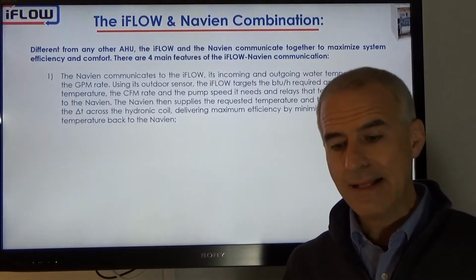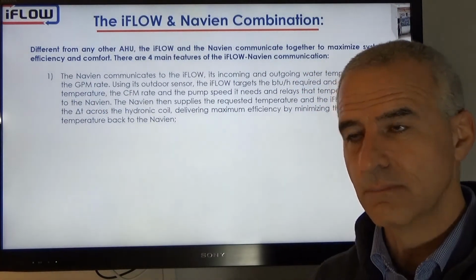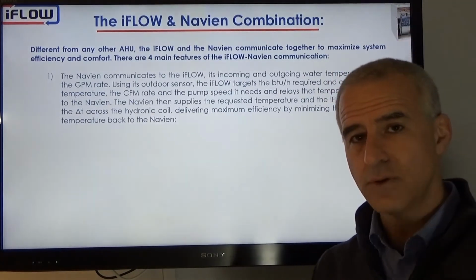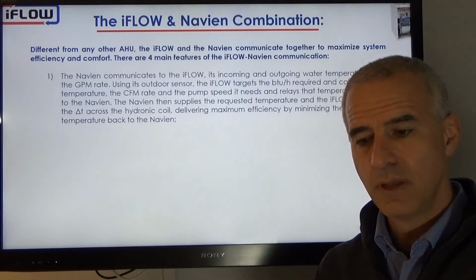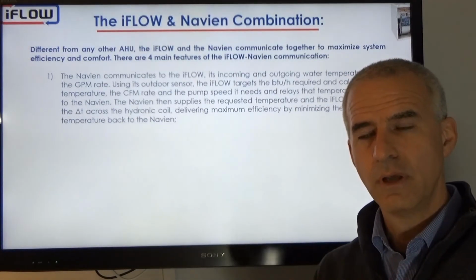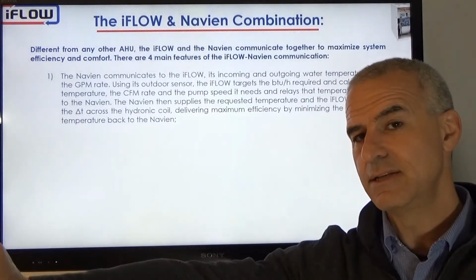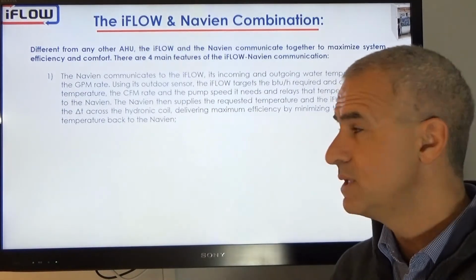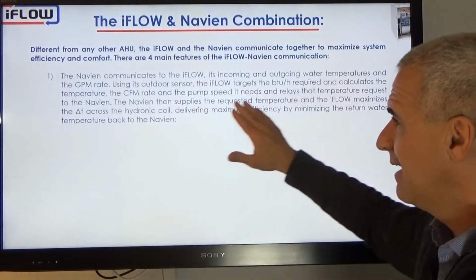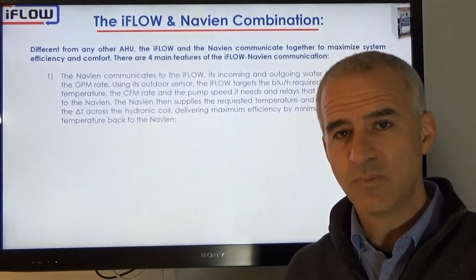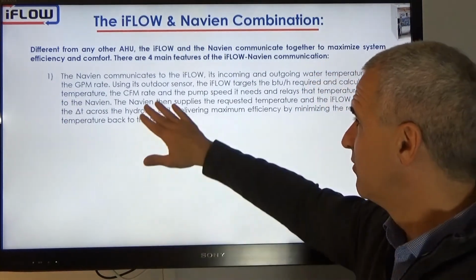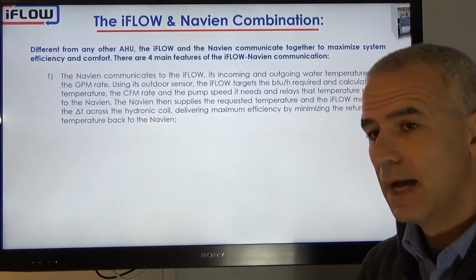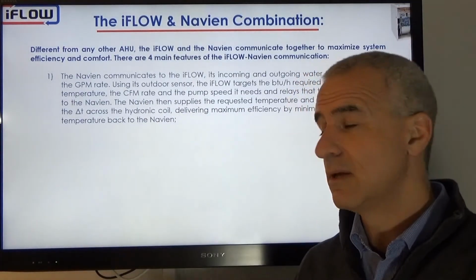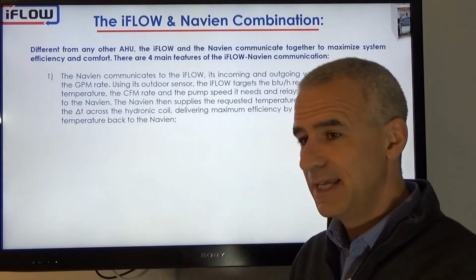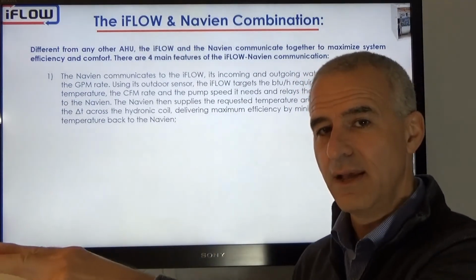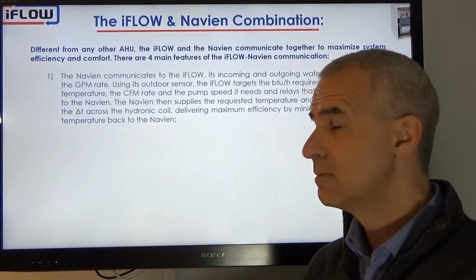The iFLOW has an outdoor sensor. It's looking at the outdoor temperature, using its reset curve, and then deciding how many BTUs I need to deliver into the house based on the outdoor reset curve. So then we calculate the temperature that we need, the CFM rate that we're going to deliver, the flow rate, the pump speed, because we control the pump speed from the iFLOW. We calculate that, and then we relay to the Navien, okay, I need this temperature, right? So I need this temperature.